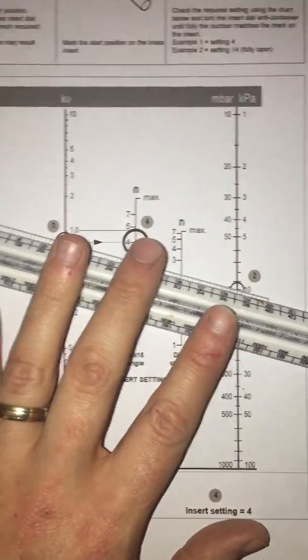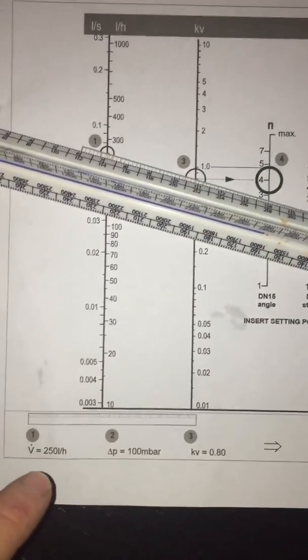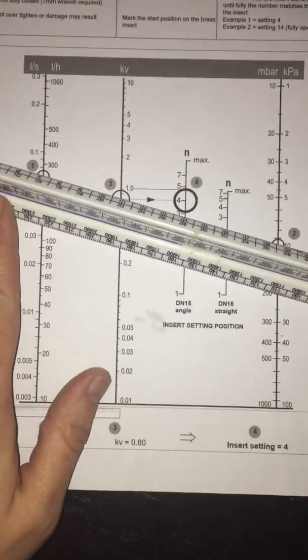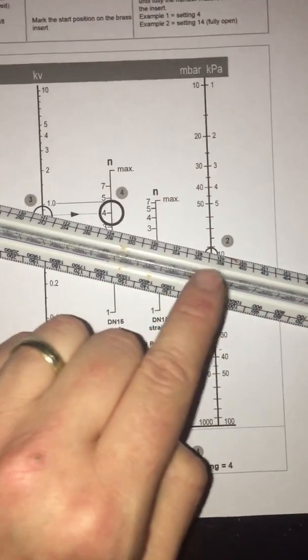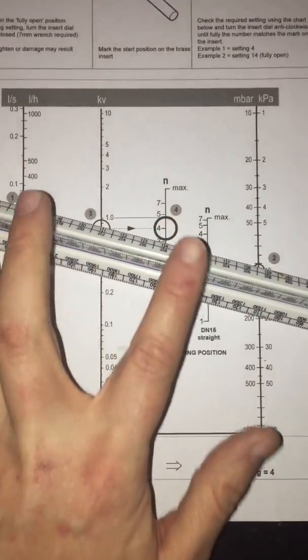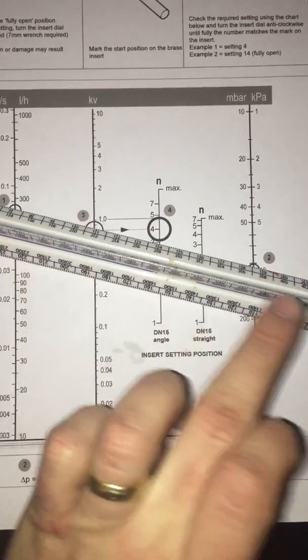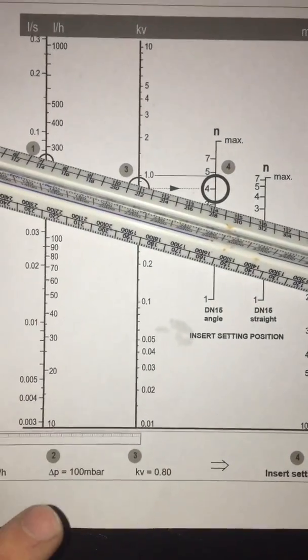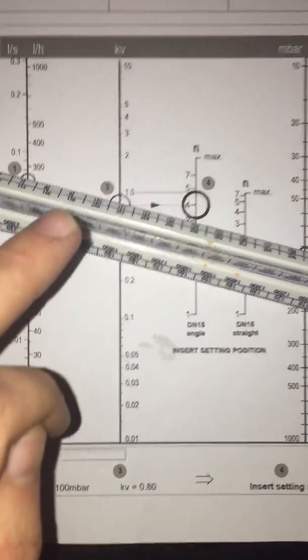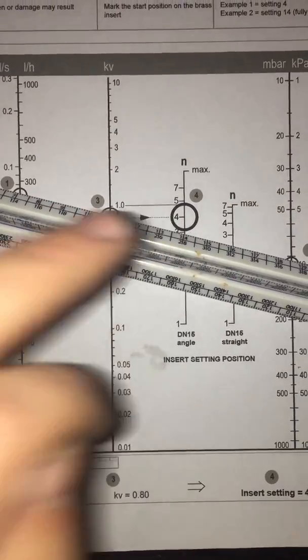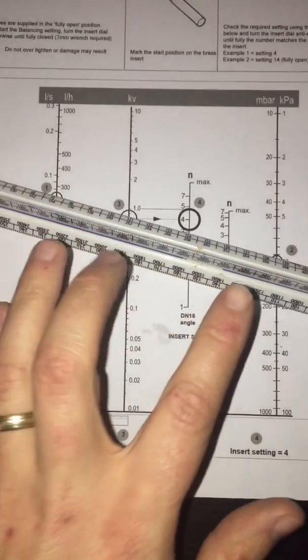Okay, so let's say in this example here, they've used 250 litres per hour and 100 millibar delta P across the valve. Okay, so for that, if we want that flow rate at this pressure drop, we need a KV value of 0.8 which will give the balancing ring setting of 4.